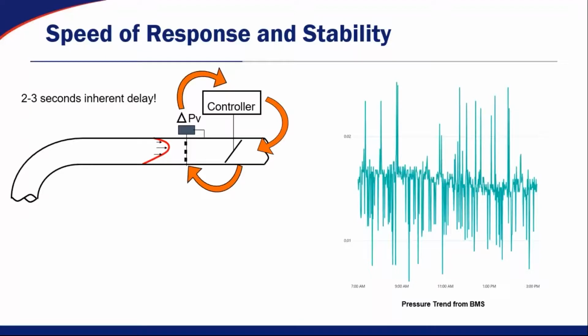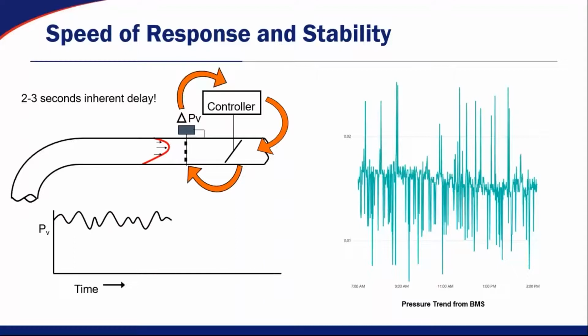And typically that'll give you about a 2 to 3 second delay if you want quick controllability. But if you're measuring airflow and you want fast control, what it's going to give you is unstable airflow or unstable pressurization control in the room and in the ductwork. So every time that VAV box blade changes position in the ductwork, it's going to change the velocity, which makes it react, take another measurement, and then readjust. We call this hunting, because effectively, even if you have a VAV box set at a constant CFM value, it's always going to be moving to try to maintain that set point.